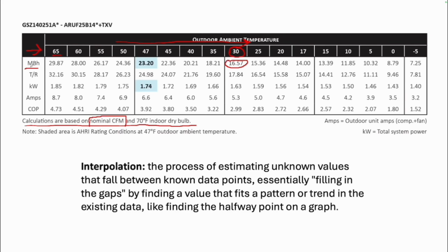16,570 BTUs. Remember, this is MBH, so we have to multiply by 1,000. So that's 16,570 BTUs. And look, right there, the manufacturer is telling us what the equipment should be able to do. And then the next one is 25 degrees. And at 25 degrees, it'll be 15,360. So, what do we do if our temperature is in between that?